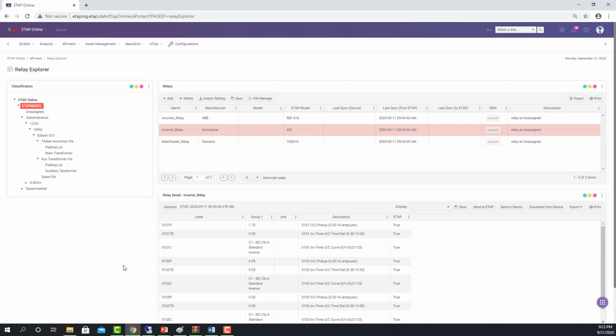Again, it's device agnostic, so you can get different manufacturers, different brands, communicate to the ETAP digital substation, download the information, and centralize the settings, and have them very quickly available when you get into the substation. So it simplifies the data collection whenever you're going to do system studies. So again, if you're using ETAP for system analysis, with a click of a button you can take these settings and send them into your ETAP model, and save time and save money in short.